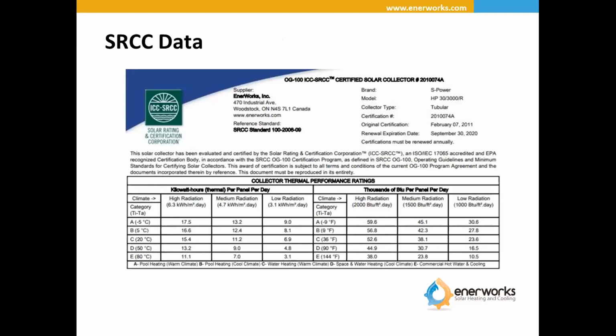So most collectors that you're going to use are certified through the ICC SRCC rating. Over here is where I tend to design to, so it's category D, full sun. Some people will use category C, particularly with flat plate collectors, because there's a big difference. The higher the temperature you go, the less efficient the collector is. So you can see that for warm water heating in a warm climate, the collector itself will produce 52,600 BTUs per day on average. But in space heating or water heating in a cool climate, it's 44,900 BTUs per day.